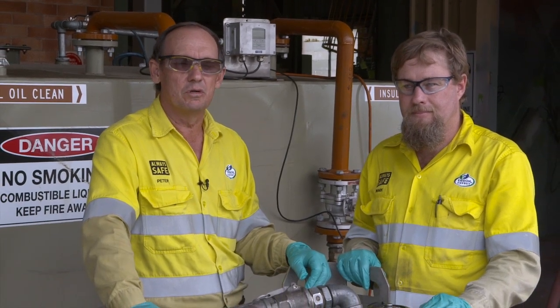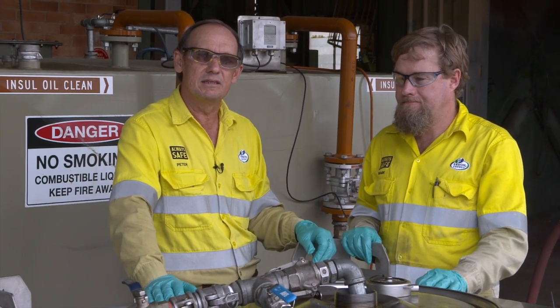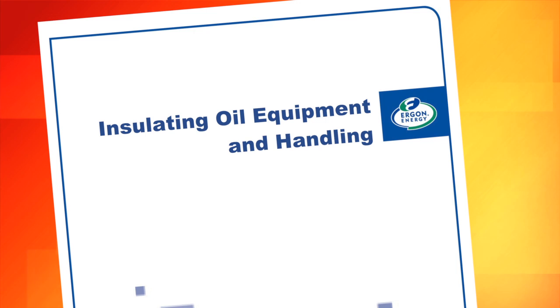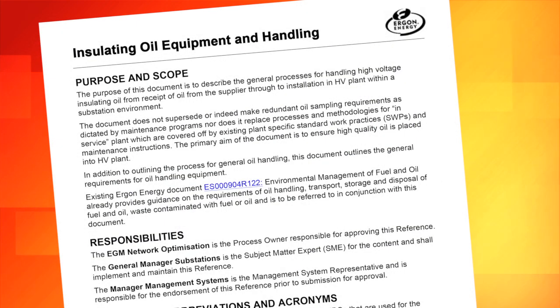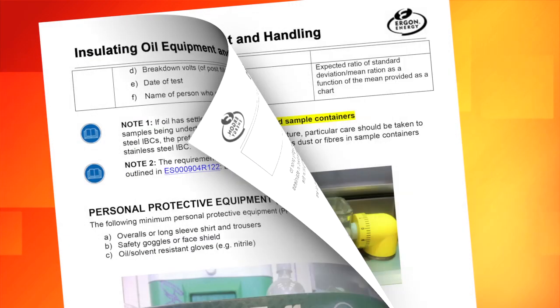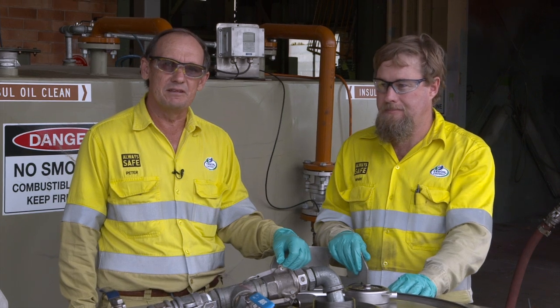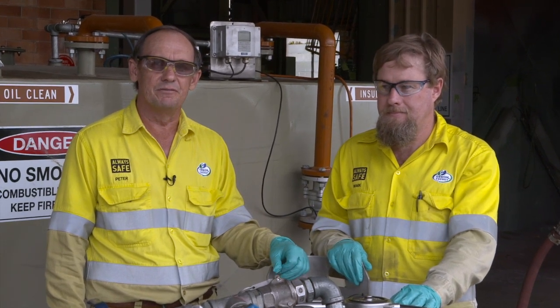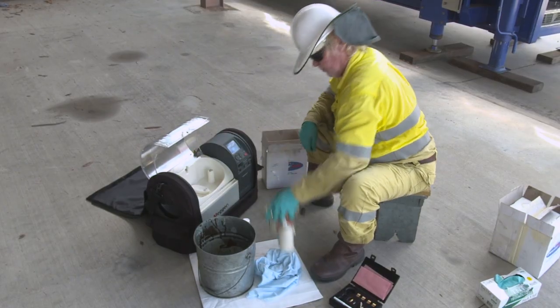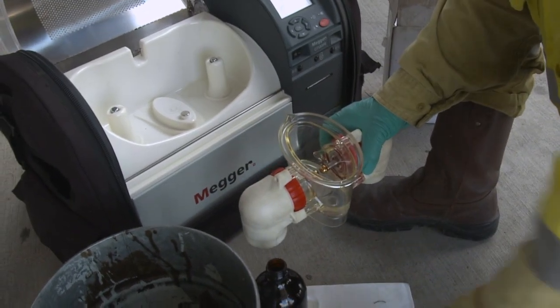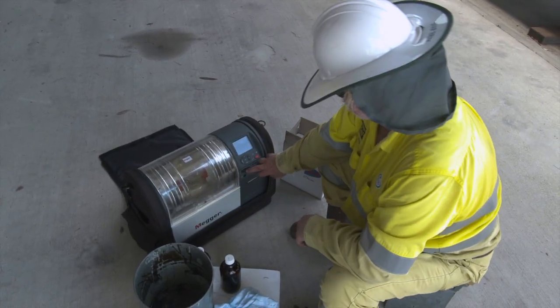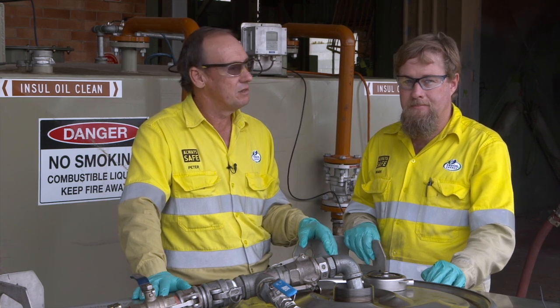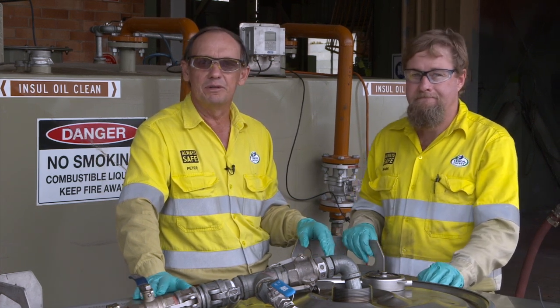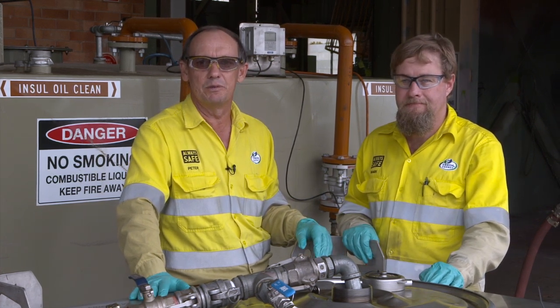Ergon Energy has introduced a new standard to ensure that we only place high quality oil into our substation HV plant in a safe and consistent manner. The standard, which is now on the process zone, covers the handling of oil from the receipt from the supplier right through to placing oil into your plant in a substation environment. The standard does not cover any of the sampling of oil that's already covered under your existing maintenance standards. It's also primarily targeted at substation plant. We're not looking out in the distribution world at this point in time.